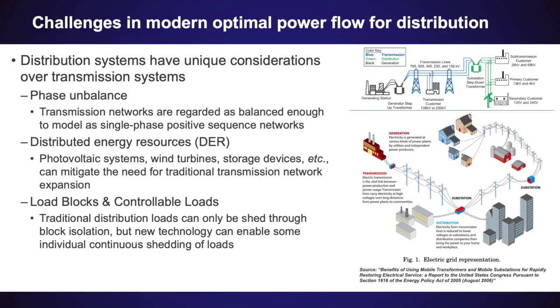There's also been a remarkable increase in the penetration of what we call distributed energy resources, like solar, wind, and batteries, which can mitigate the need for traditional transmission network expansion, but don't have the same types of cost functions as traditional generation. Finally, there are also unique demands for load shedding, which is important for contingencies such as network faults that come from extreme events like hurricanes or wildfires, where in transmission systems loads are considered to be continuously sheddable, whereas in distribution it contains a mix of loads that can only be shed by isolating whole blocks, and more recently some individually controllable loads such as electric vehicle chargers and HVAC systems.